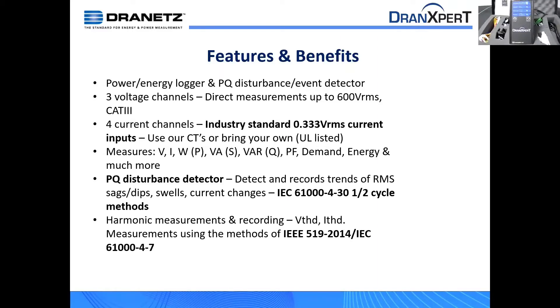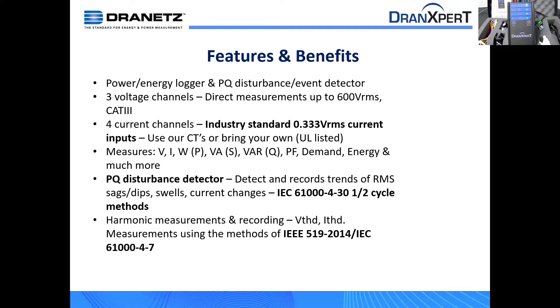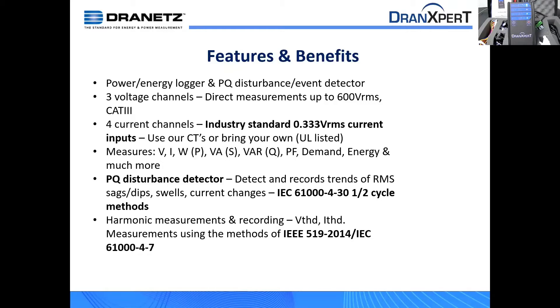So that's an important thing to note. And the same for CE. Internationally, CE would be the reference. We are CE-certified on our instruments, as well as the CTs are CE-referenced. So again, this is a PQ disturbance detector that does have half-cycle recording capabilities of our more expensive products. It is not IEC 61,000-4-30 compliant, but it does share some of the techniques and measurement capabilities and measurement methods of that. And similar to harmonics, it follows the same basic fundamentals of IEEE 519-2014, as well as 61,000-4-7, but is not compliant with these standards. So this is a basic reference instrument for harmonics and power quality, but it does provide that ability for you as well.